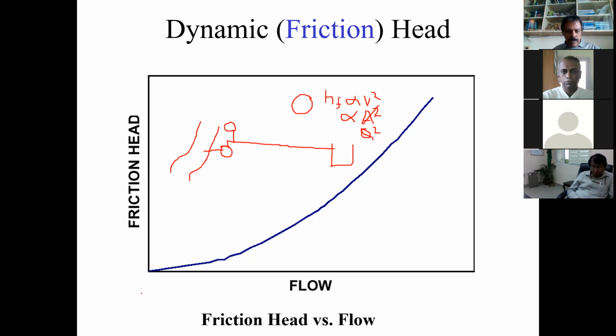So here it means that if you put 10 meter cubed of flow into the pipeline, it is going to have this much friction. If you put 50 meter cubed of flow into the same pipeline, this is going to be the friction head. If you put 100 meter cube, this will be the friction head. So the pressure gauge actually shows the system resistance, the resistance offered to the flow by the pipeline. And this is parabolic, obviously, because it is proportional to the square of the flow. This is a pure friction head, that means a system without any static or vertical lift, only horizontal transfer of liquid through the pipeline.